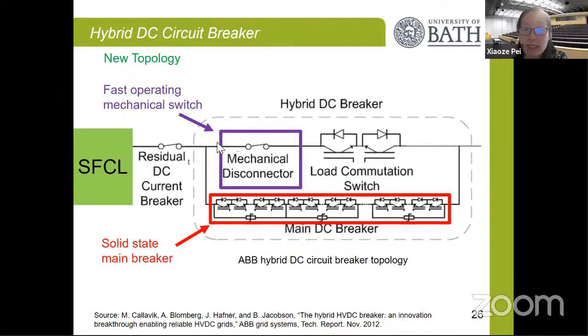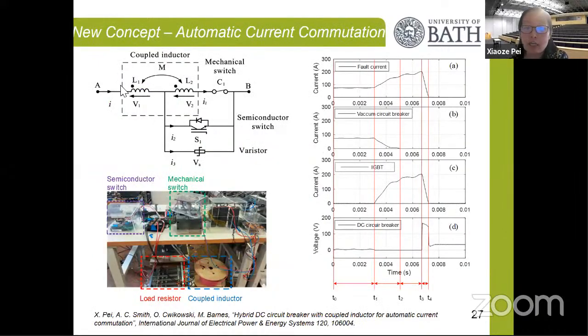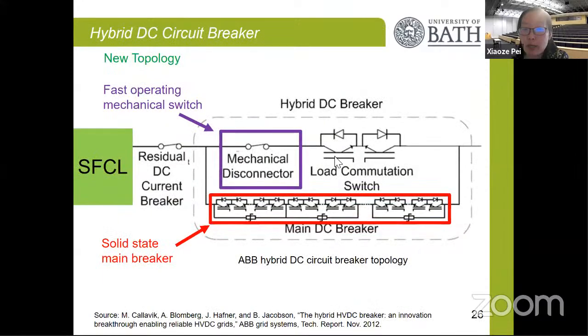One way is to reduce the contact resistance of the mechanical switch. This is already quite matured technology. Another important area is the design of the load commutation switch, because it is made of low voltage MOSFETs, and it normally uses quite a lot of them connected in parallel in order to reduce the losses. So we came up with this new concept of using a coupled inductor for the current commutation, because in this way we are able to remove the need of the load commutation switch and reduce the losses during normal operation, which provides a high efficiency operation.